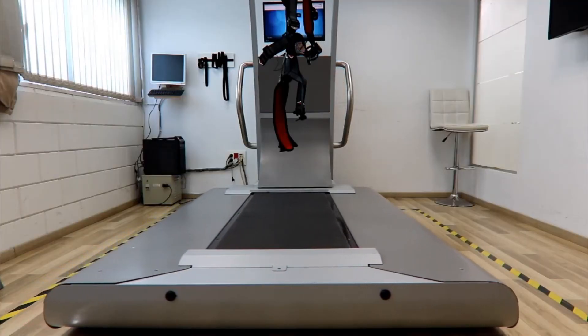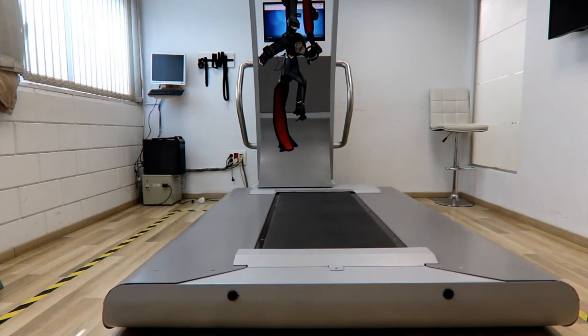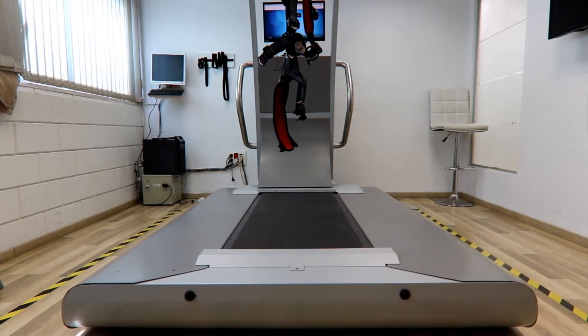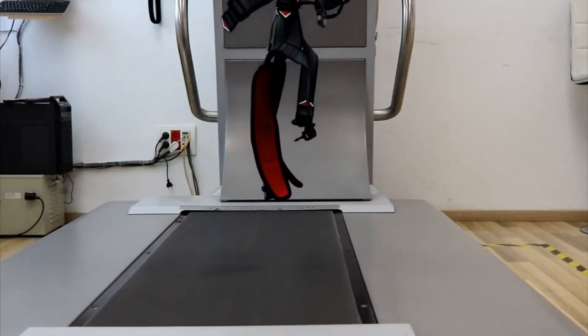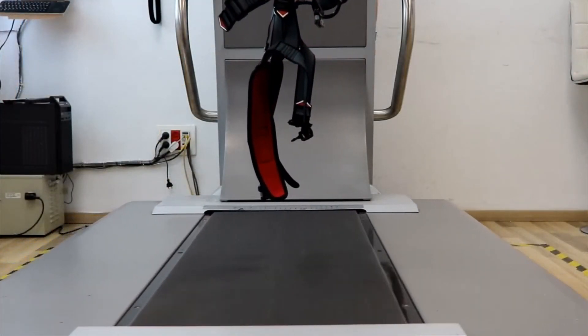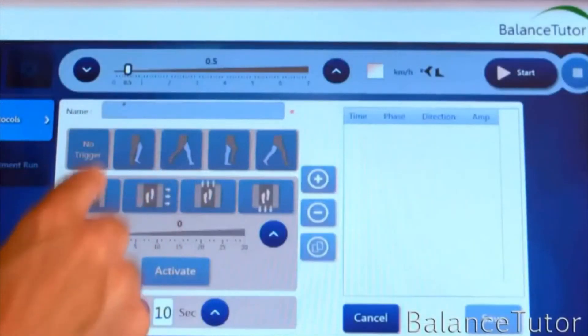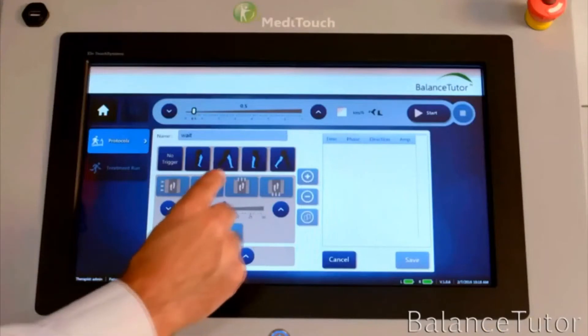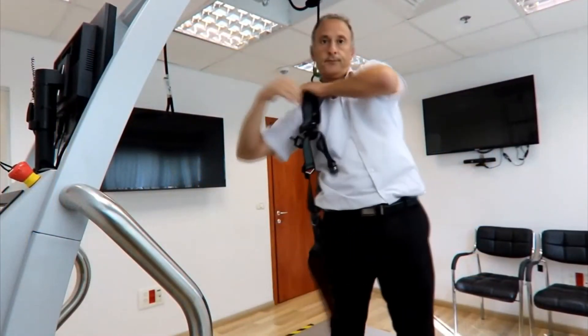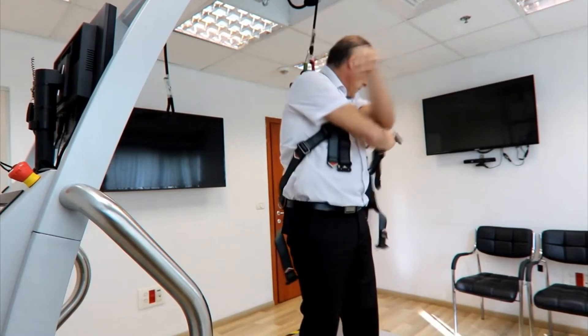The Balance Tutor perturbation treadmill allows for customizable and safe medial-lateral (left and right side) perturbation. In addition, anterior and posterior perturbations can be triggered. These perturbations can be achieved while the client is standing and during gait. The perturbation protocol is easy and quick to customize to the client's ability. Safety features include a harness and emergency stop, and the system allows for fast client setup to fit into the busy clinic schedule.